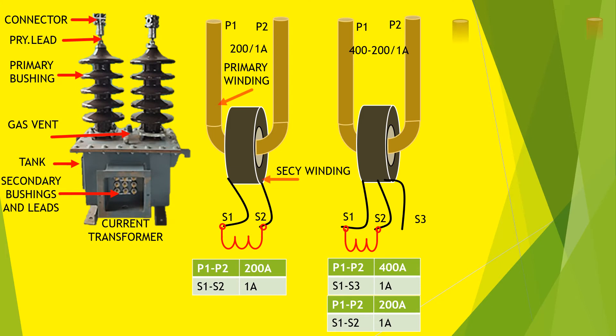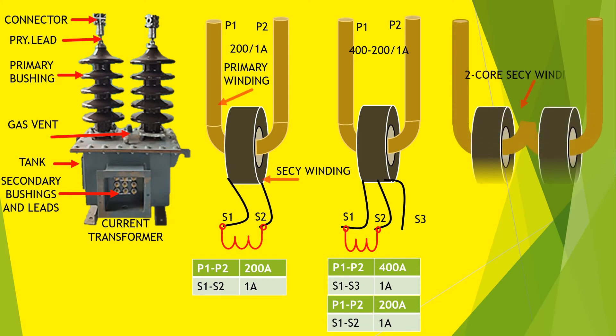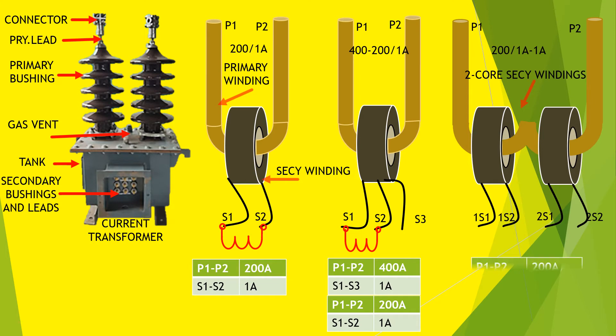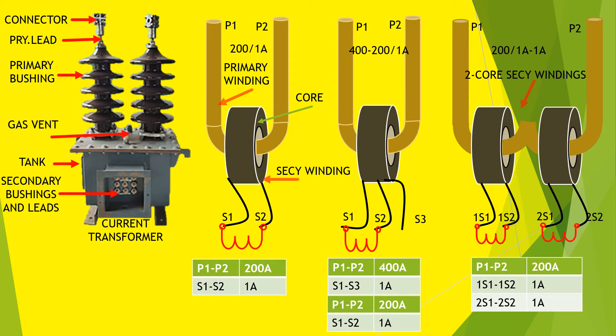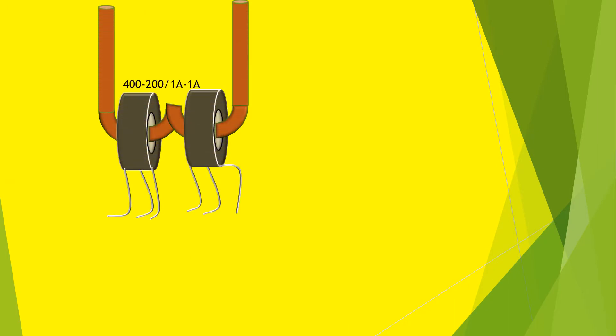In the third picture, the rating is 200/1 ampere, meaning the secondary has two cores: 1S1 and 1S2, and 2S1 and 2S2. Current flows at both secondary windings is 1 ampere when 200 ampere normal current flows along P1 and P2. The CT has two secondary core windings used for two different purposes.